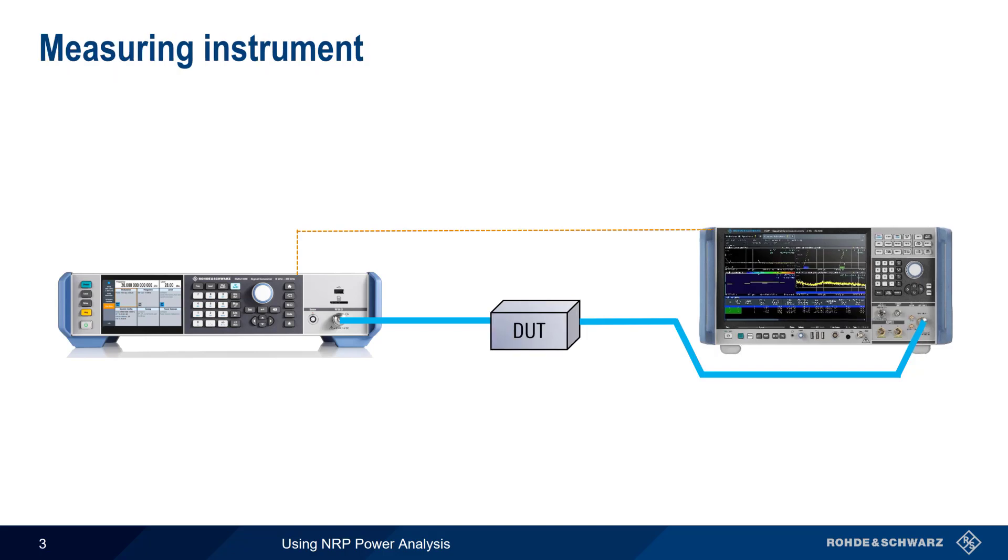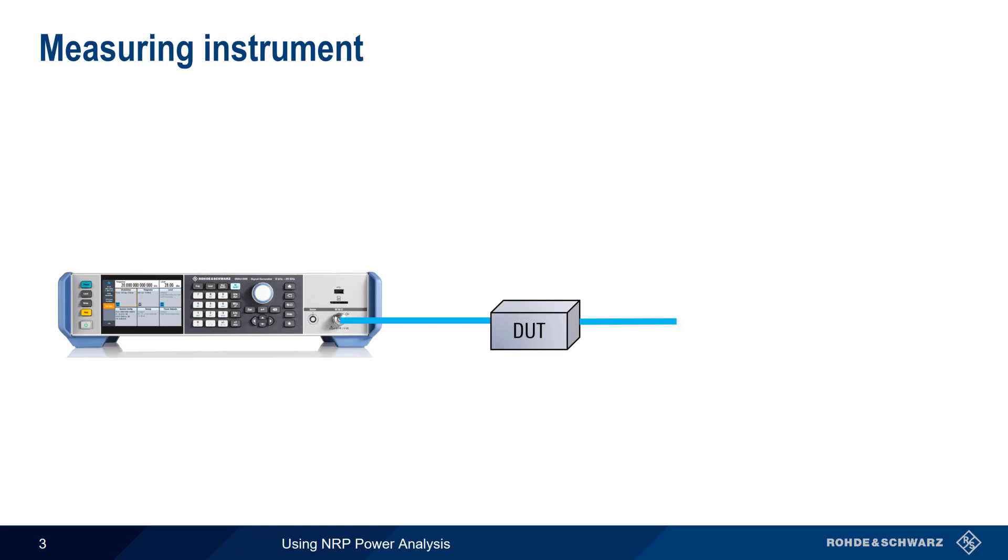For some types of testing, especially when the signals involved are vector signals, a spectrum analyzer is the best choice for a measuring instrument. However, for many types of tests involving scalar measurements, a simpler and more cost-effective solution is using a power sensor as the measuring device.